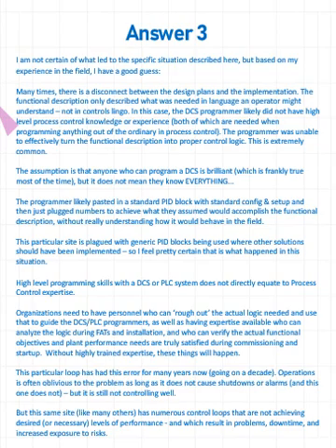So basically, in this case, once everything's done, they get the system kind of running, and then they forget about this. The process, if you look at the history, it's terrible. It's fluctuating. It's at two different set points. It's all over the place. Not good process control, and history shows it very clearly. But since it's not tripping the plant, let's not worry about it. That's just a mentality thing. That's a culture thing, really.